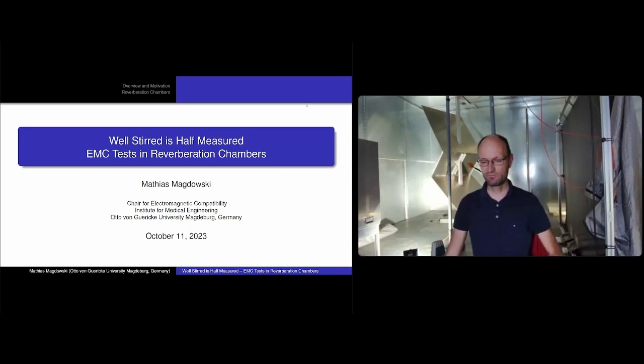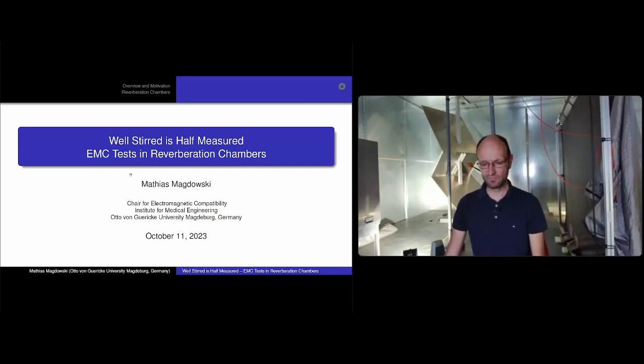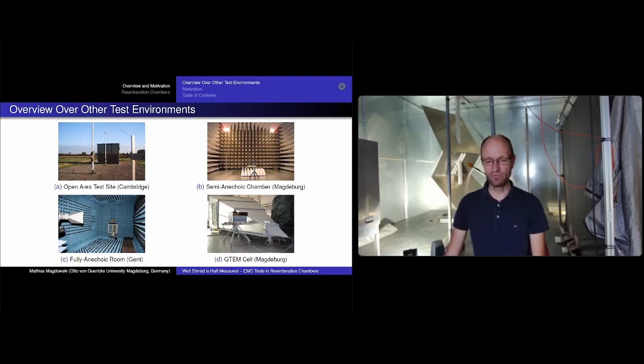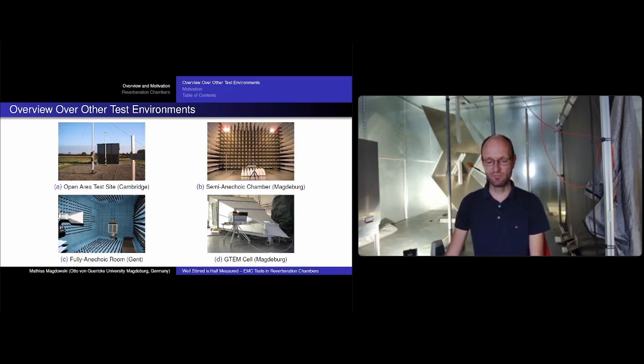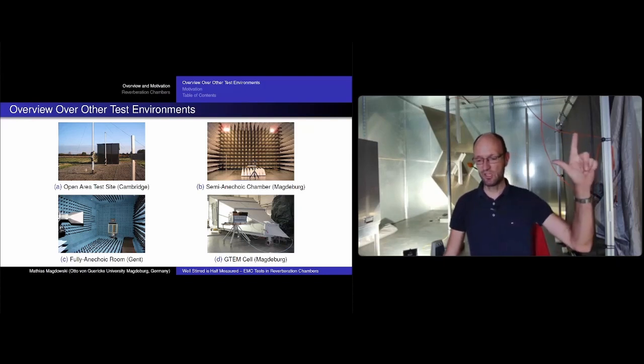Let's start with an overview of the test environments typically used for EMC tests. The simplest one is an open area test site: you take two antennas, put your EUT somewhere in an open space, measure coupling between the EUT and the antenna, and make sure the ground has a nice conductivity.